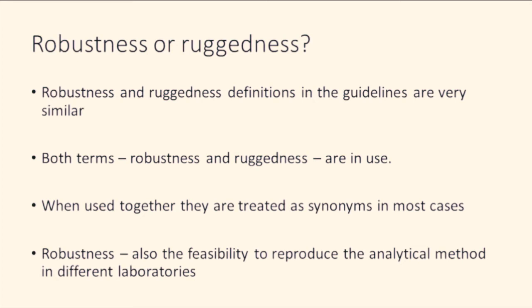The previously introduced definition implies changes made to the method within the same laboratory. However, robustness can also be described as the feasibility to reproduce the analytical method in different laboratories under different circumstances without the occurrence of unexpected differences in obtained results.